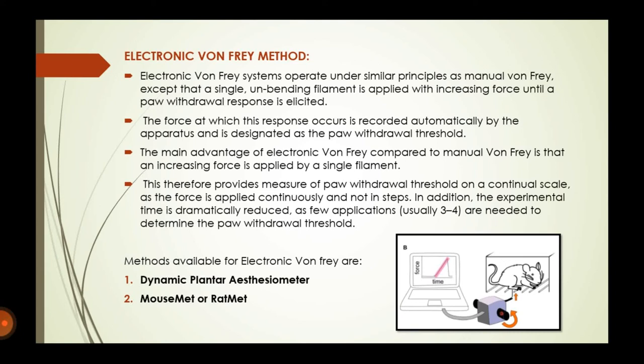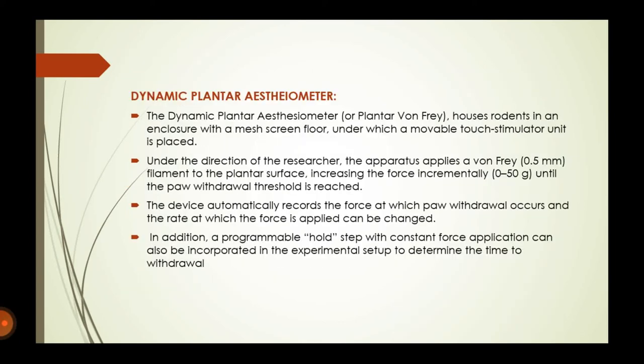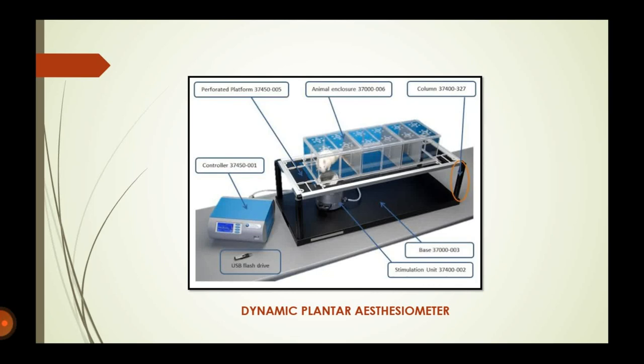Methods available for electronic Von Frey include the dynamic plantar aesthesiometer and the MouseMet or RatMet. The dynamic plantar aesthesiometer has a mesh screen floor under which a movable stimulator unit is placed. The apparatus applies a 0.5 mm filament to the plantar surface, increasing force until the withdrawal threshold is reached. The device automatically records the force at which paw withdrawal occurs, and the rate of force application can be changed.